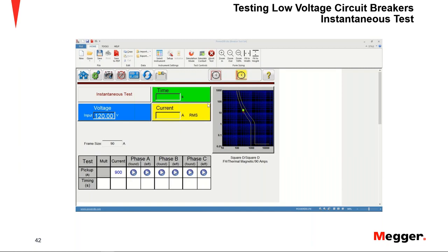Pretty similar, right? We switch to this screen, right? Looking at the instantaneous, same thing. We have now our current will be 900 amps, right? Automatically selected by the software using 10 times the rated current of the breaker under test. So let's go ahead and run the first measurement on phase A. And same process, the unit will have to determine what tap is in use, determine the impedance, and start testing.